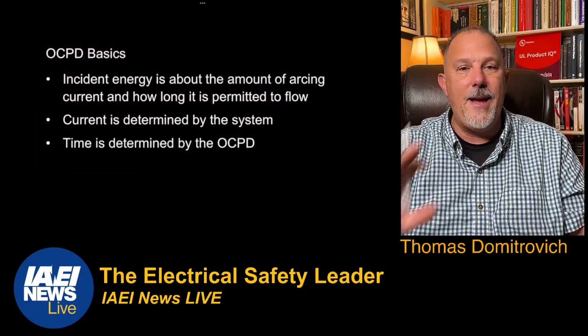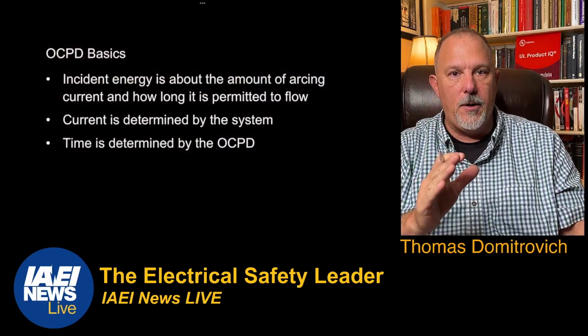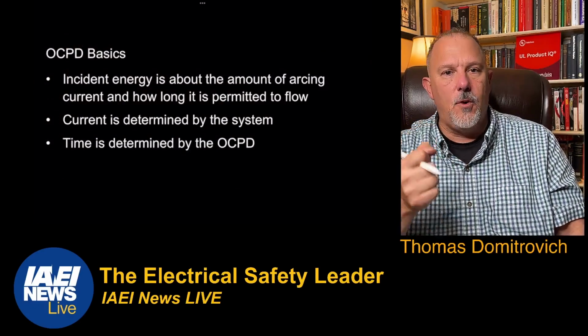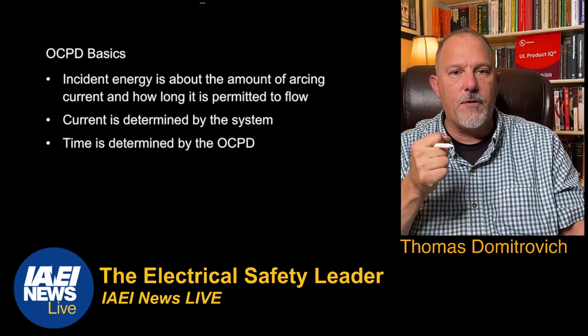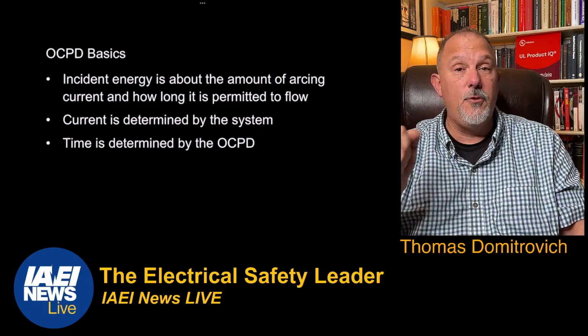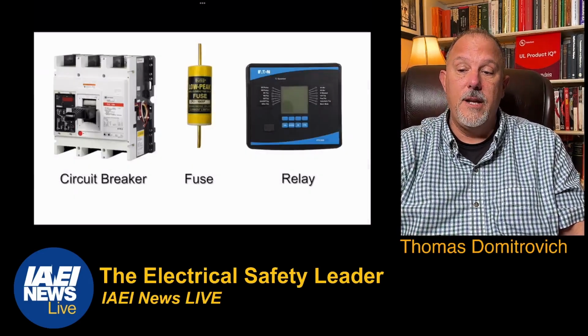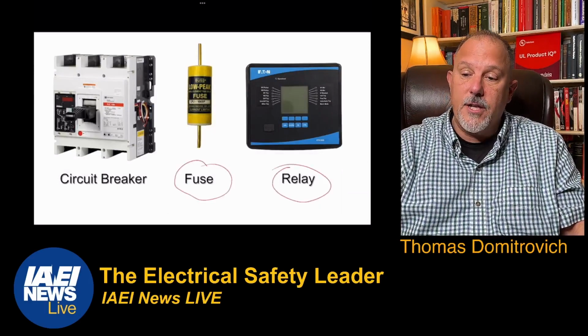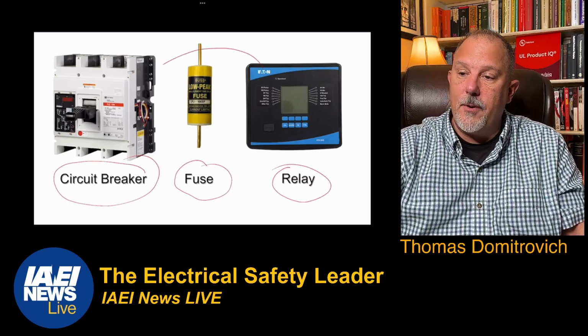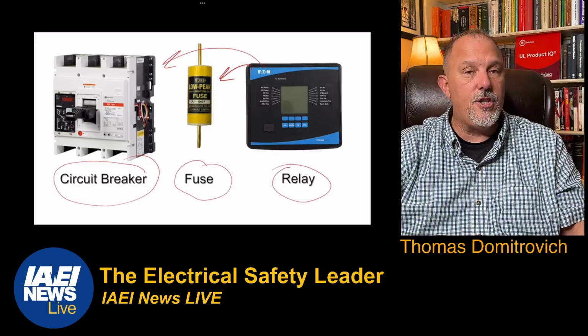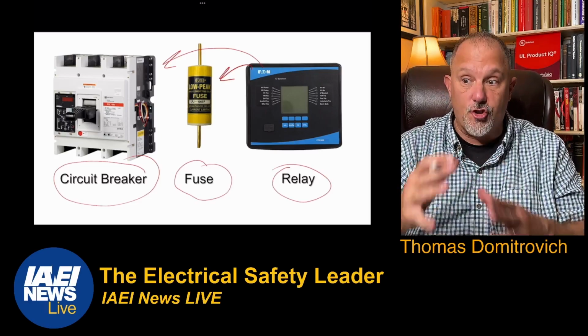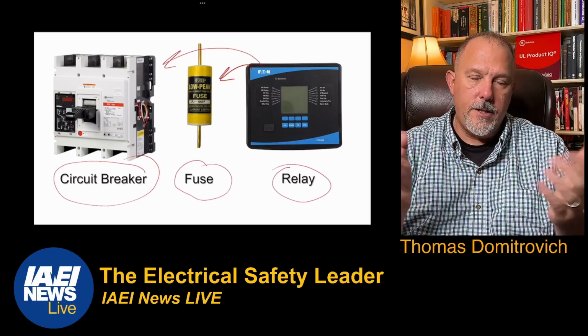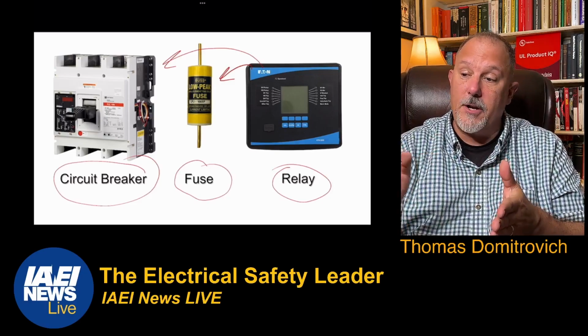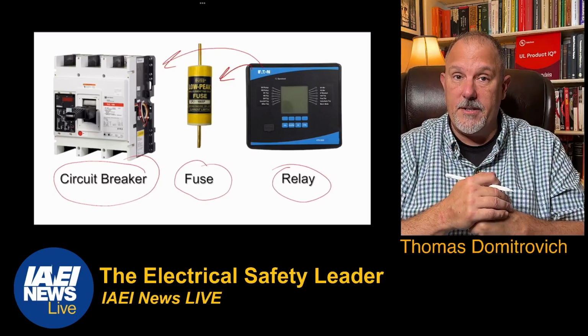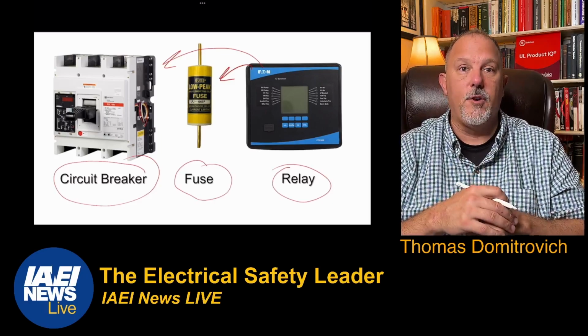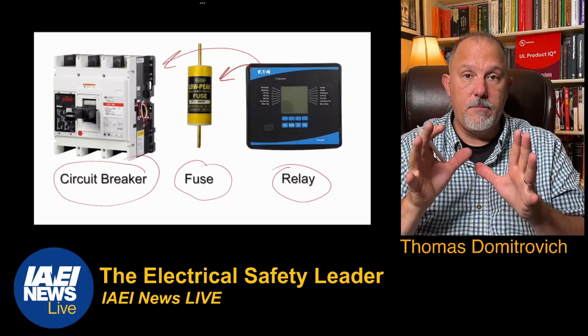Incident energy is about current and time. Now, your protecting overcurrent device. Remember, the only way that I can control the amount of time that any value of current is permitted to flow is through the proper application of an overcurrent protective device. What are my options? I can have relays, I can have a fuse, and I can have a circuit breaker. Relays will eventually operate a circuit breaker or the switch that's part of a fusible switch scenario. There are shunt trippable switches on the market. It's a no-brainer that I can shunt trip a circuit breaker. And that's a molded case circuit breaker. I typically would use a relay on much bigger equipment, so your large power circuit breakers or your medium voltage circuit breakers. But a relay does play into this picture.